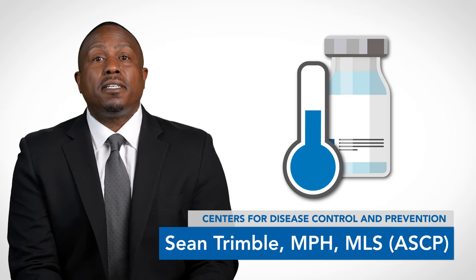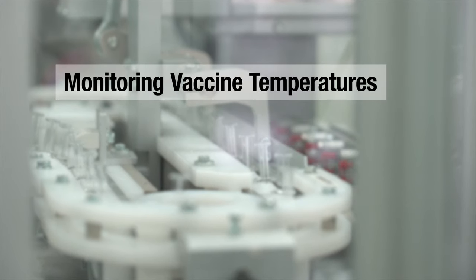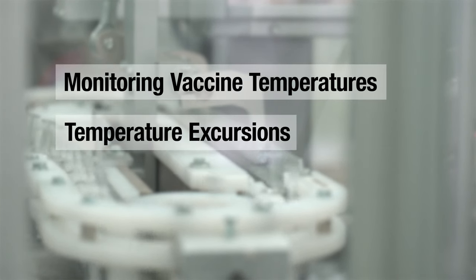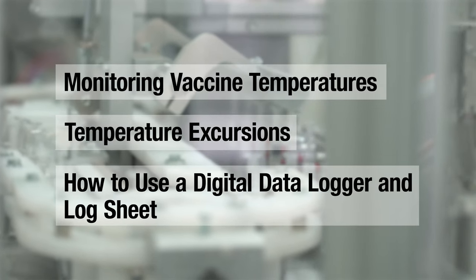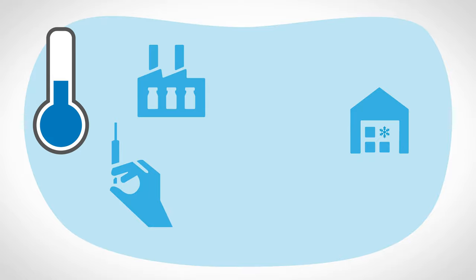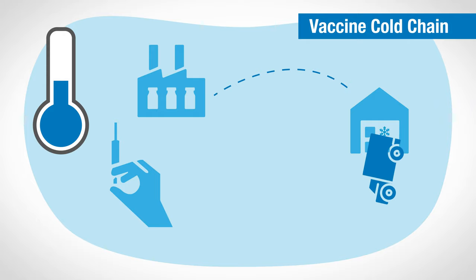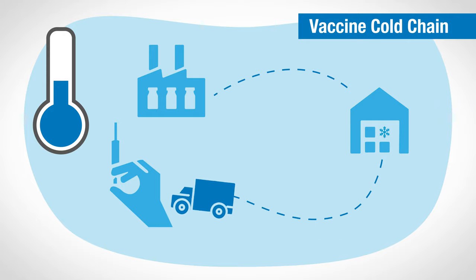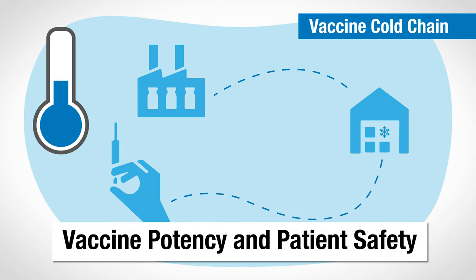When storing and handling vaccines, it's critical to have proper temperature monitoring equipment and procedures to maintain the cold chain and protect patients from receiving compromised vaccines. In this short video, you'll learn about monitoring vaccine temperatures, temperature excursions, and how to use a digital data logger and log sheet. Vaccines require a temperature-controlled environment until they are administered. This is known as the vaccine cold chain and includes all vaccine-related equipment and procedures. Maintaining the vaccine cold chain will ensure vaccine supply potency and patient safety.